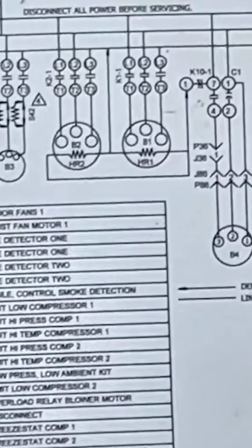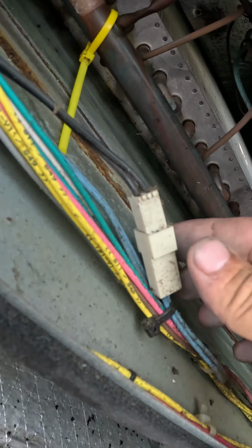S49 is a freezestat for compressor 1. Right there is our freezestat, 2 wires. And down there's another freezestat for the other compressor. There's where it plugs in to these blue wires. And if we look, TB1Y2, so that side's going straight to where it connects on the terminal board. So the other side of that blue wire is, looks like S7.